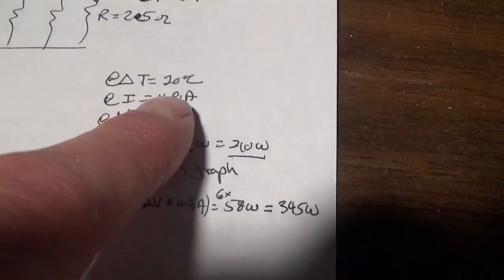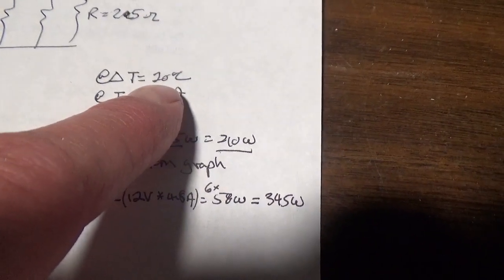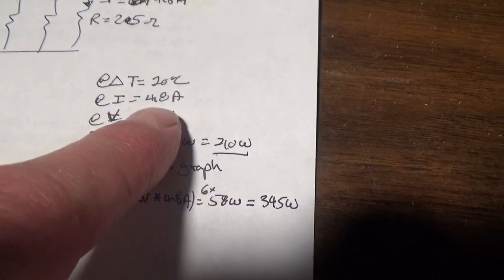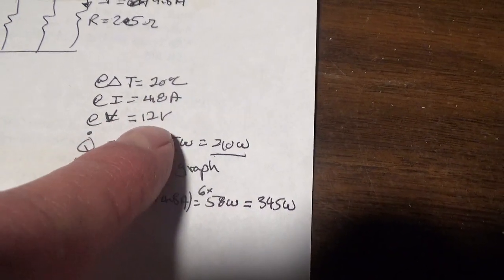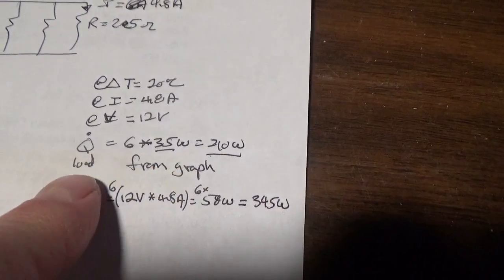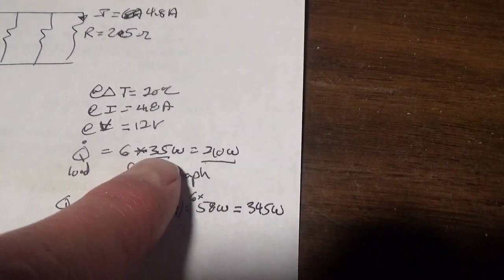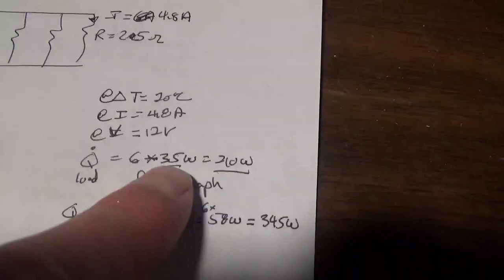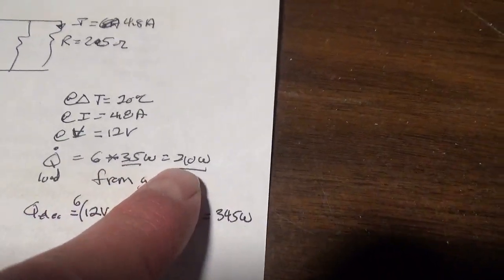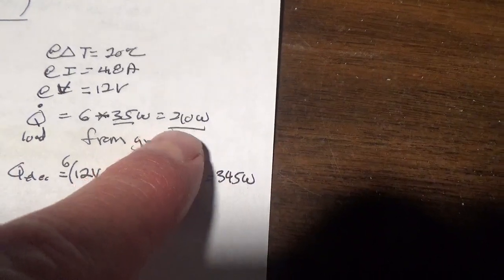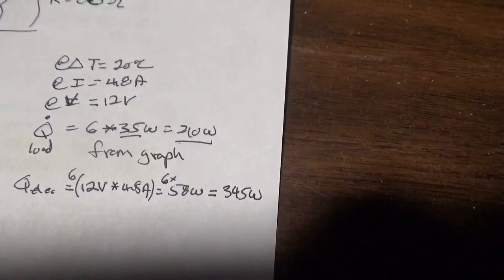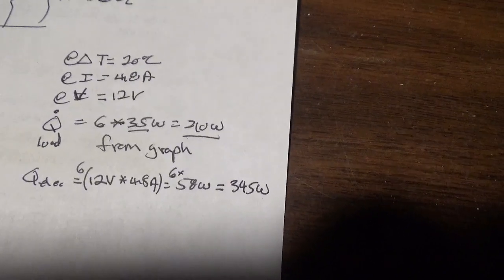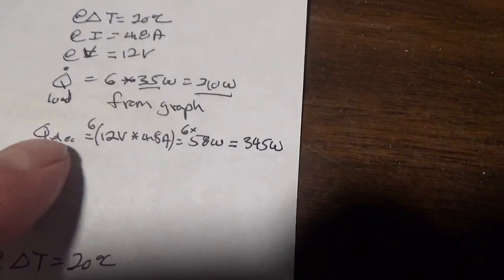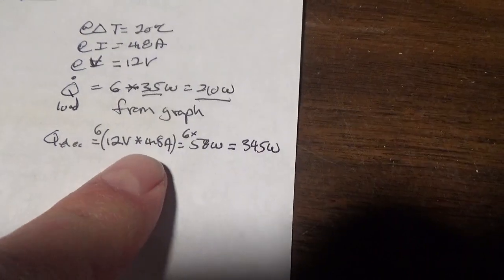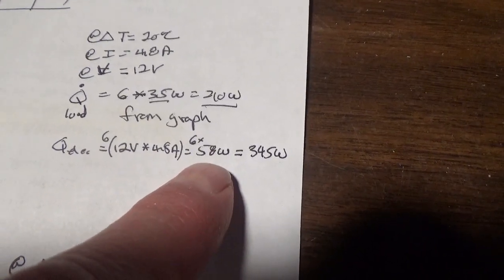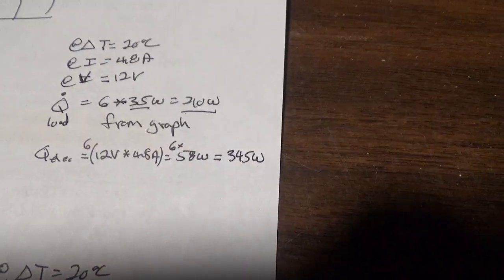We'll get a delta temperature of 20 degrees C, 4.8 amps per module, 12 volts per module. The Q load should be 6 times 35, because we have 6 of those and each can pull 35 watts, giving us 210 watts. That's what we got from the graph. In addition, we have our electrical load because we're putting power into it, so 6 times 58 is 345 watts.